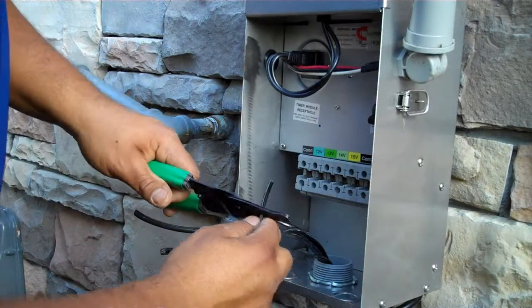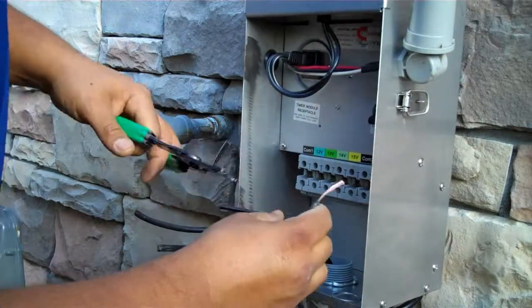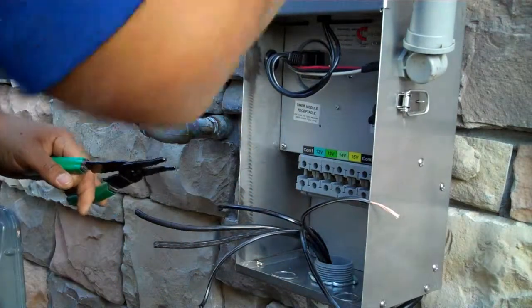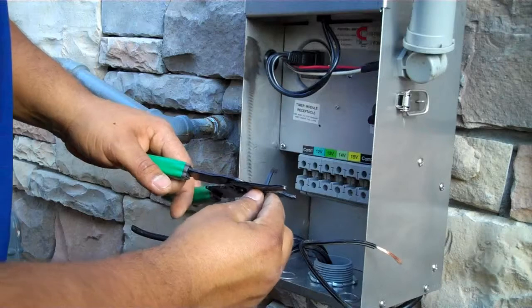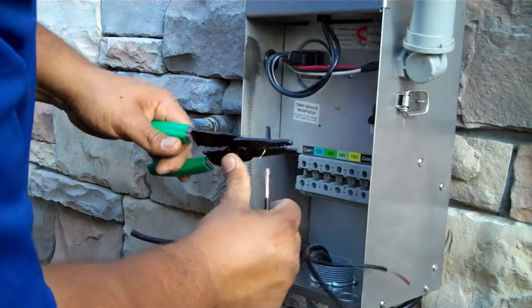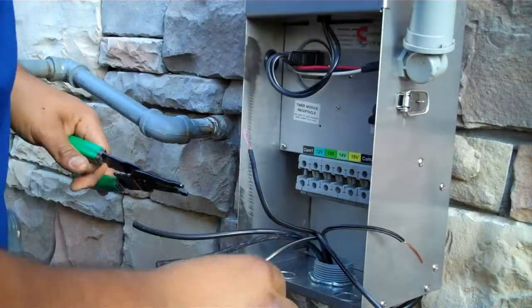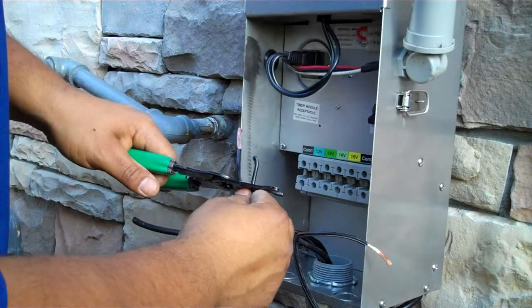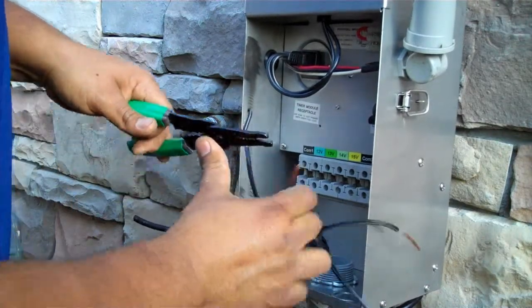Now that you have secured your transformer to the wall, you can begin connecting your wires to the transformer. First thing you will need to do is strip your power wires back at least 1.5 inches. This ensures that you get a good connection and prevents arcing.